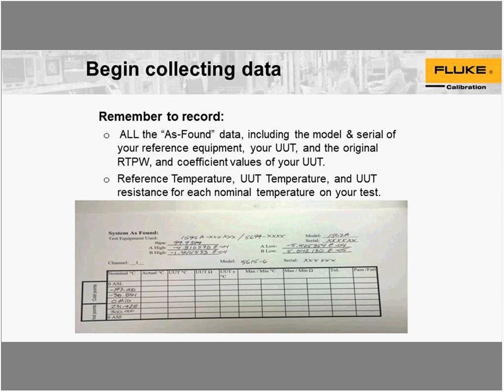Also, you need to have the reference temperatures that you are using written down so that you have them recorded. You don't want to deviate from those. When you go to do your as left, if you use different reference points, it's not the best calibration.